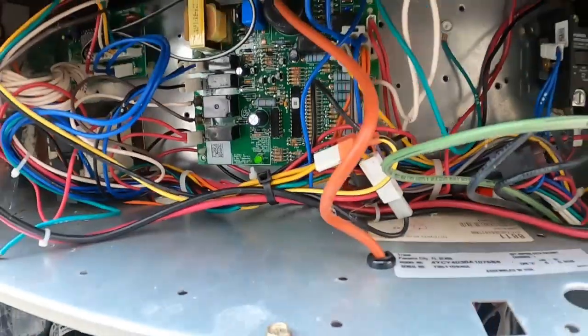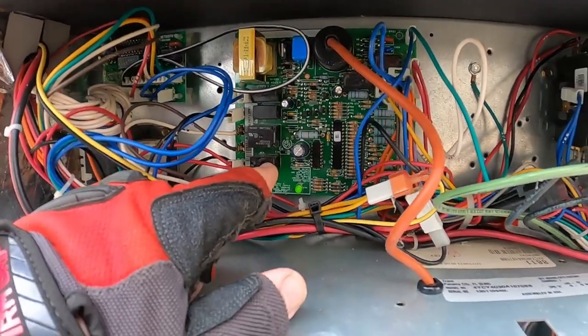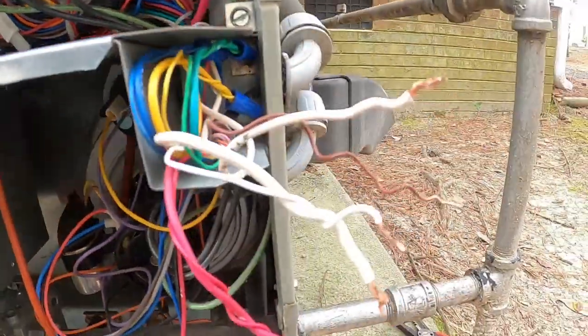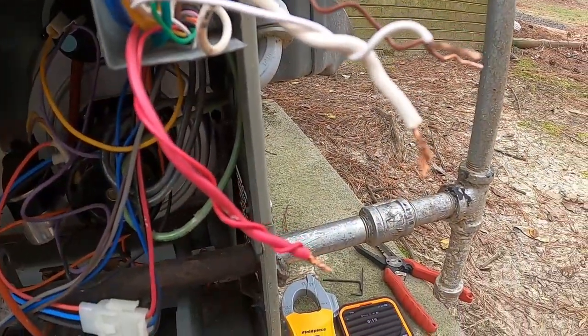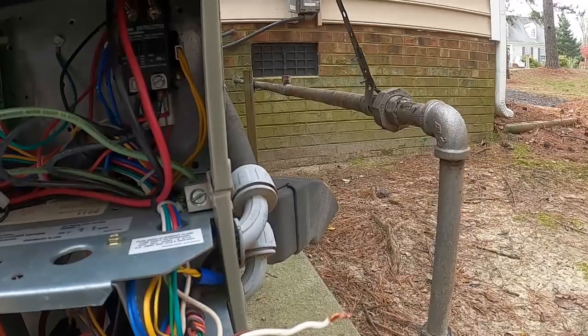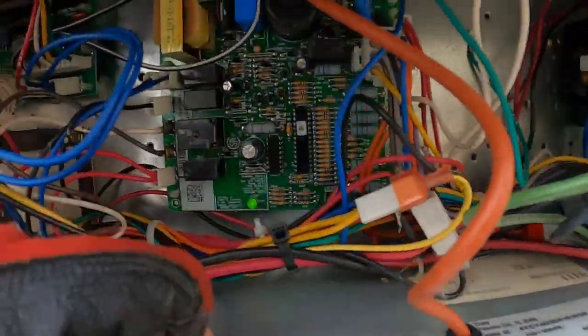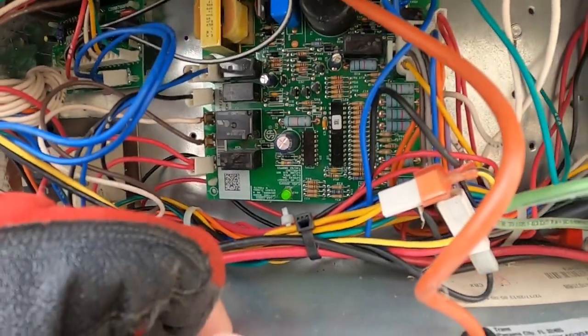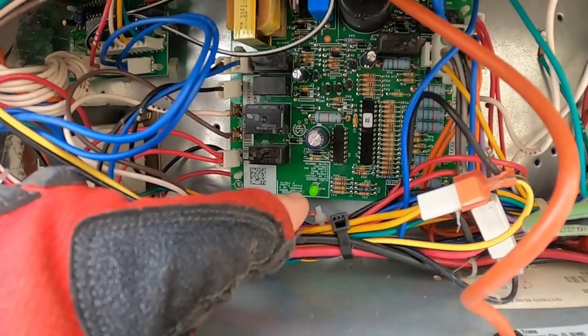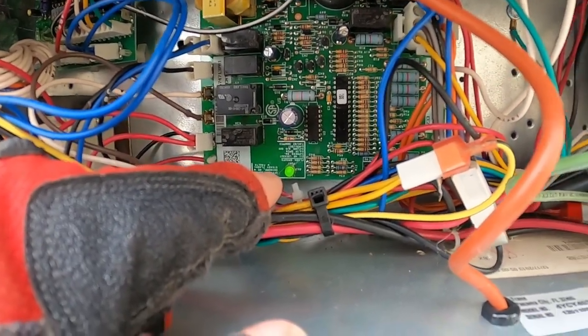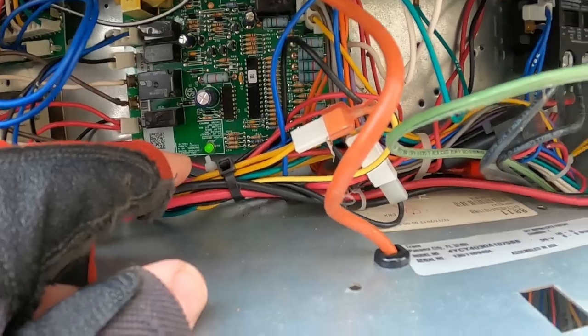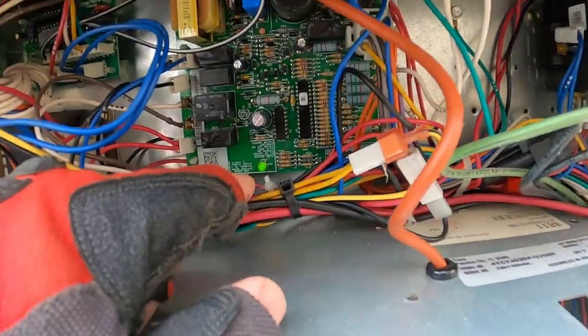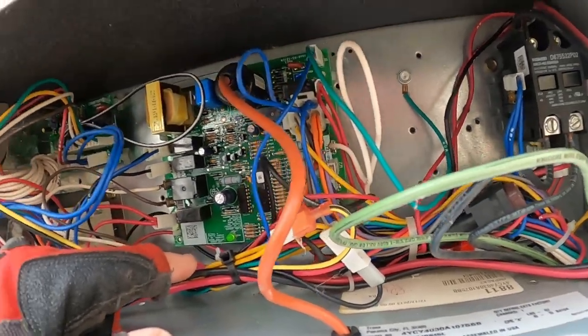But definitely got an issue with this board. Yeah, I'm not getting a call connected. I've got my wire disconnected there. You pull that disconnect out, this thing should come back on and reset itself. That light's showing its normal operation, but that draft motor should not be running. And when I send 24 volts, it should be firing off without a problem.